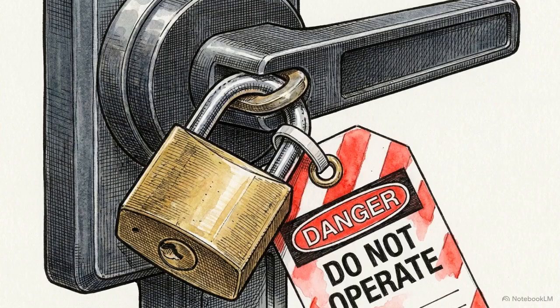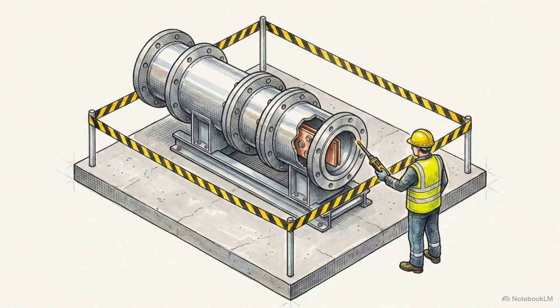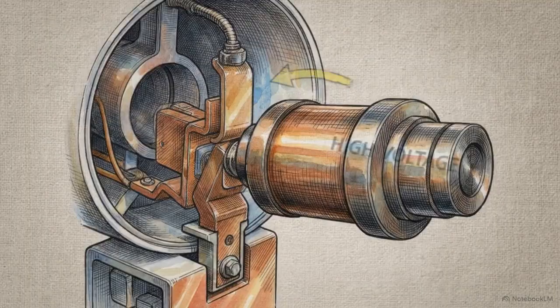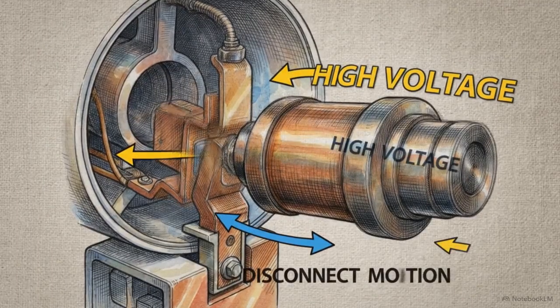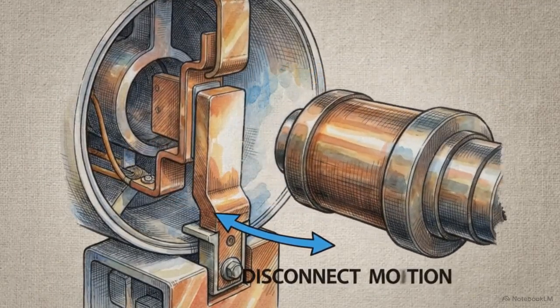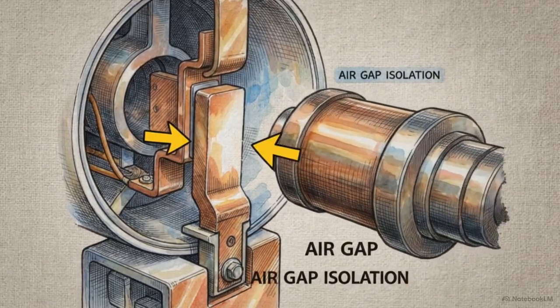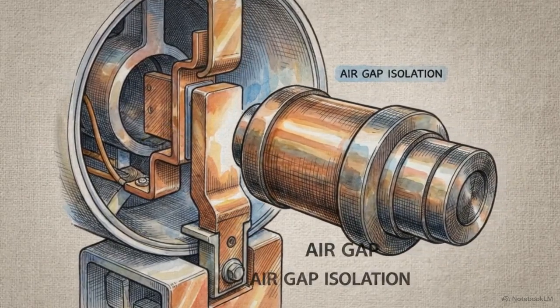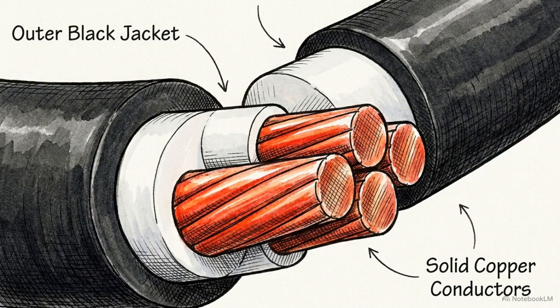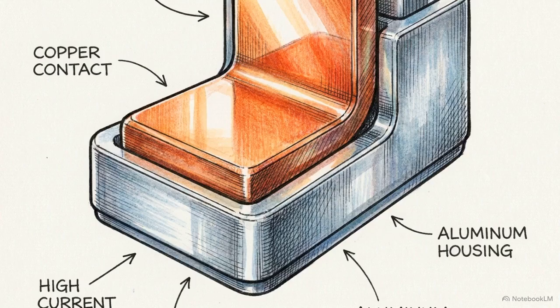These instruments cannot be connected to the switchgear until the lockout-tagout boundary is confirmed. This requires barricading the work area, establishing physical safety tagging, and verifying the absence of voltage directly with the switching authority. Physical execution of GIS circuit breaker tests begins only when equipment is physically isolated from the grid and its safety state is verified. Testing begins with static integrity to confirm the health of the insulation and the main current paths before verifying dynamic operation.